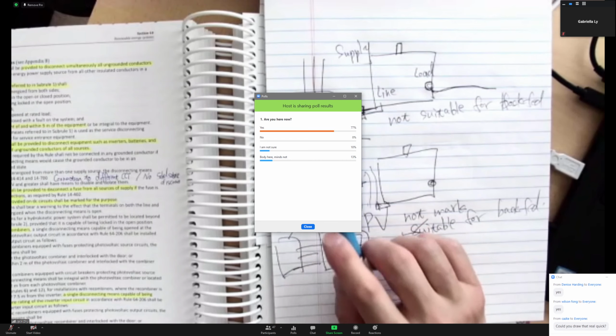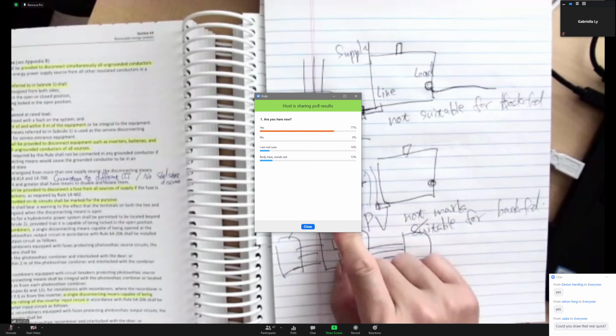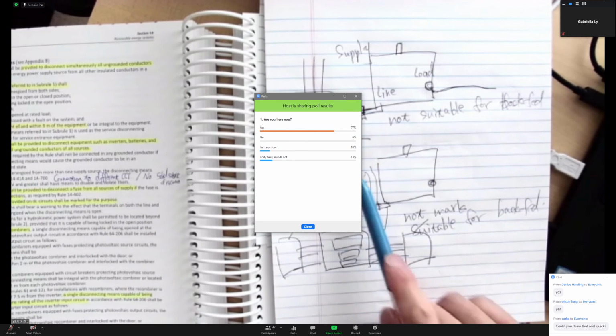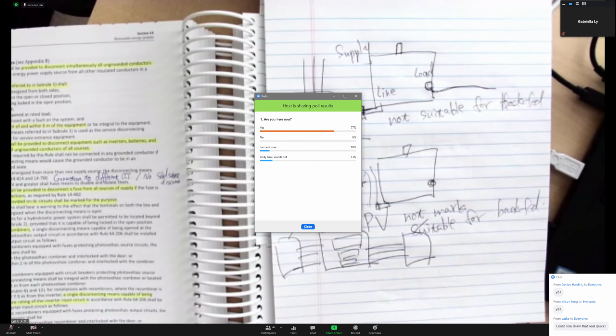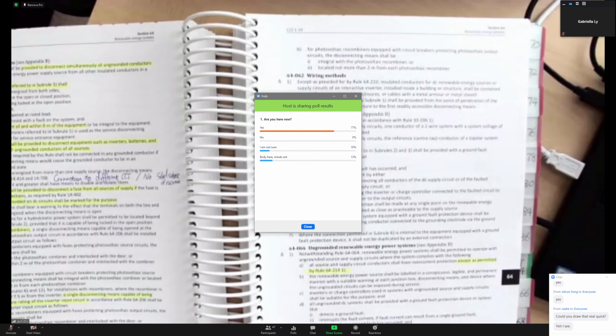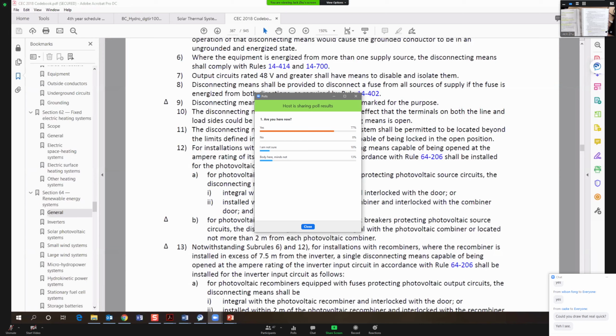Because if one of the fuses blows, you have to open the panel, you have to be able to take that fuse out. But without the secondary disconnect, the fuse is still live. That's what this rule asks of you. You should all know this. Disconnect means for a DC circuit should be marked for the purpose, right? Because when you try to break a DC circuit, the arcing and everything will be much more severe than in an AC circuit. So the DC overcurrent protection or disconnect means is rated differently than for the AC circuit.